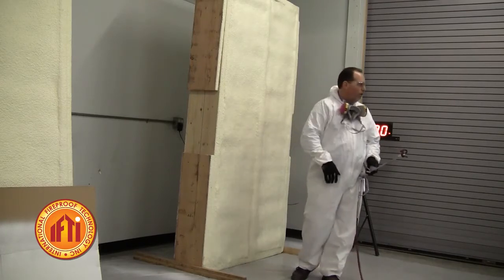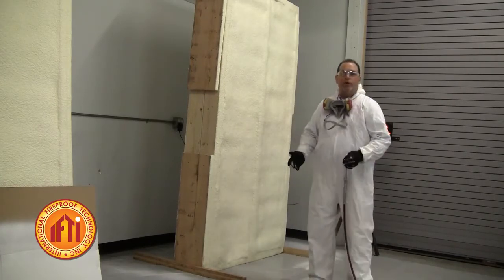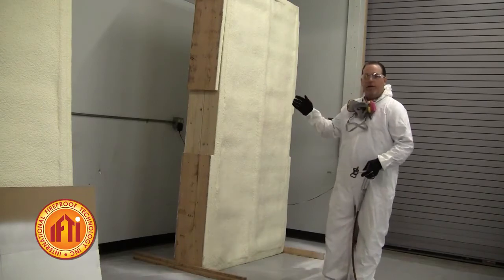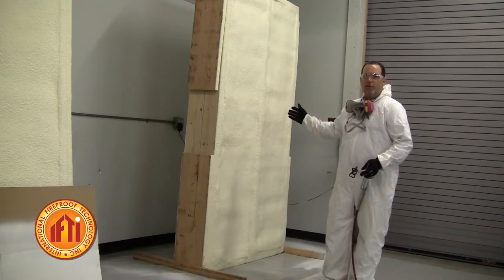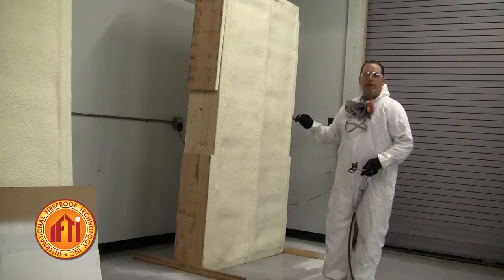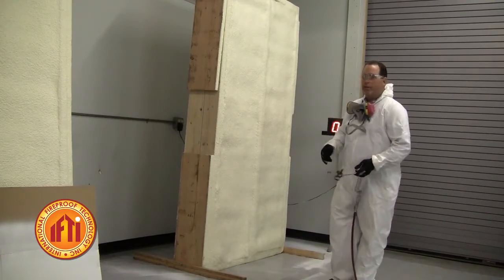So what we're going to install here is a couple of metal plates that we're going to use as our tags. As we're coating this foam, we'll put the same mils across the tags. We'll be able to do a wet mil thickness to see where we are in our application.